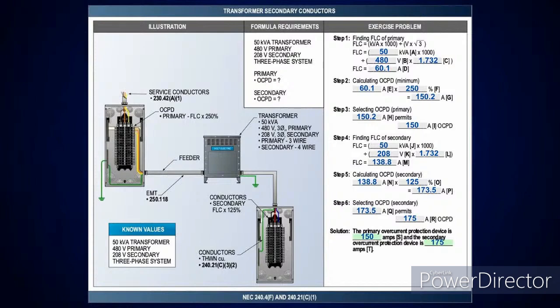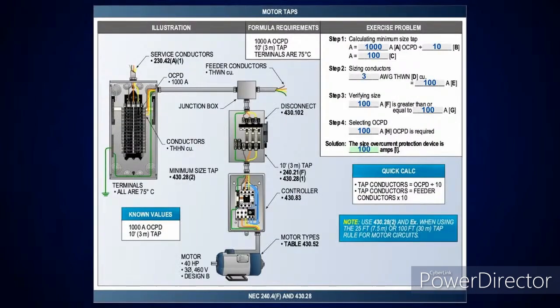Nice. If you look, I did the same calculation all the way through that. All I was doing was following what the table was telling me, and I was looking for that superscript 1. If I had a superscript 1, you went up. If it's 125% or less, you automatically knew you were going up. If I looked at any percentage in table 450.3(A) or (B) that was above 125% and didn't have the superscript 1, what did I do? I dropped down. Right.